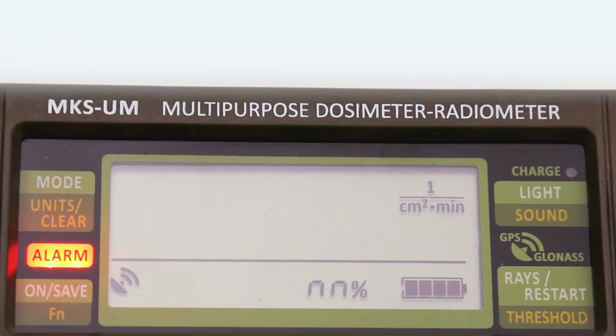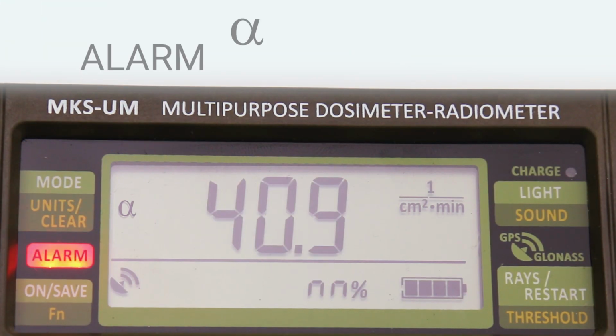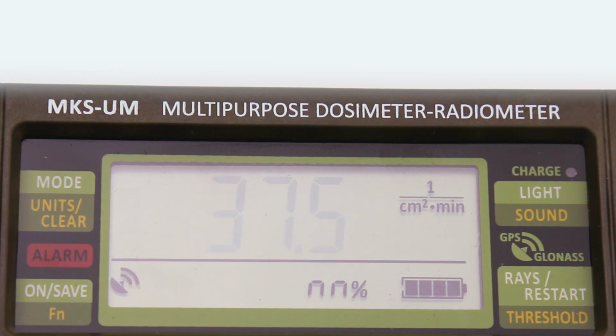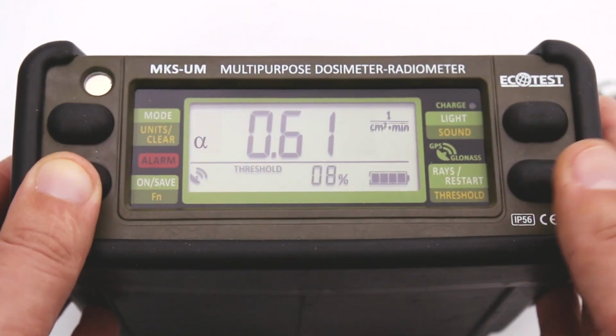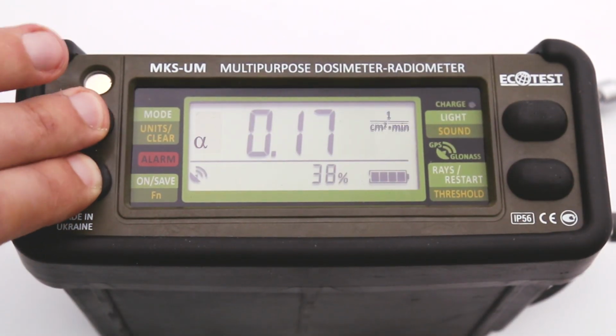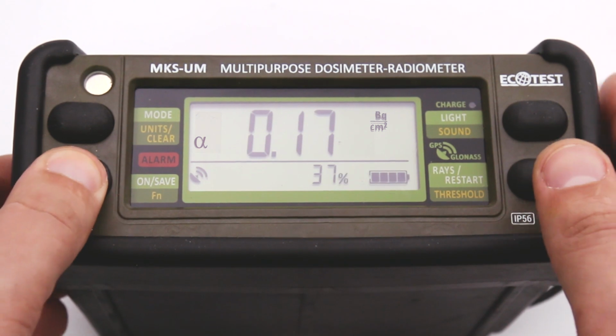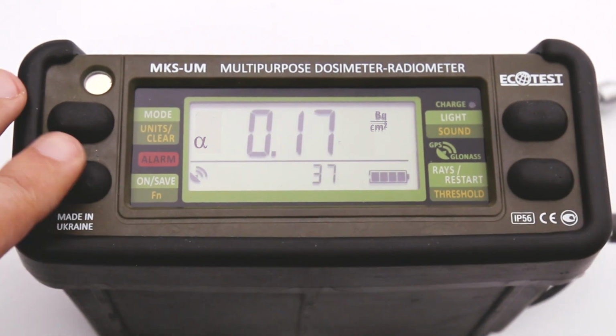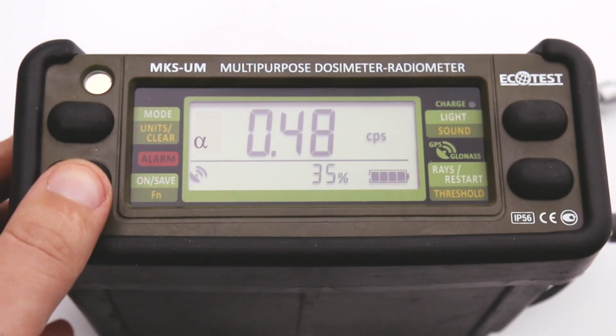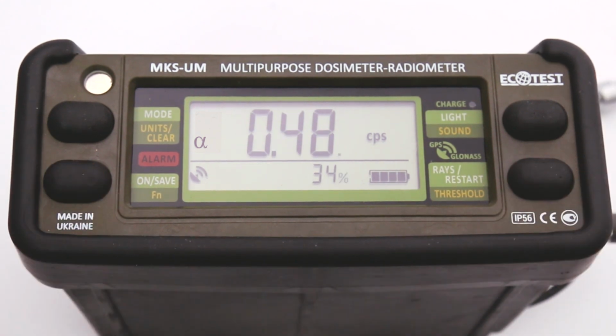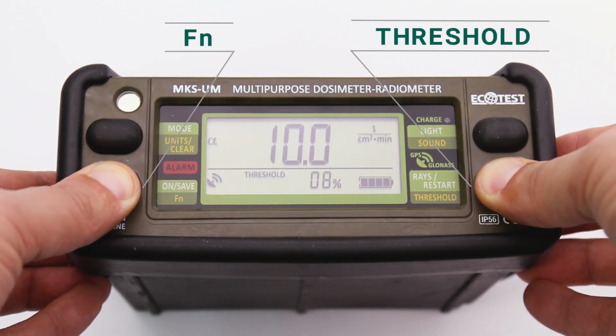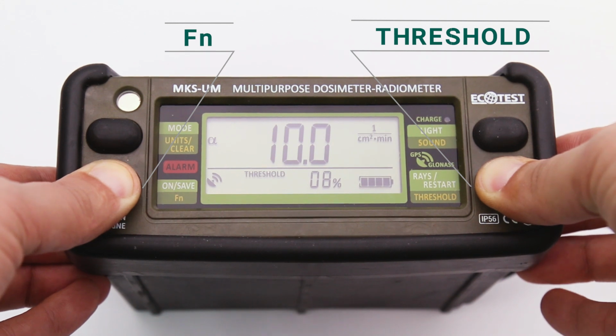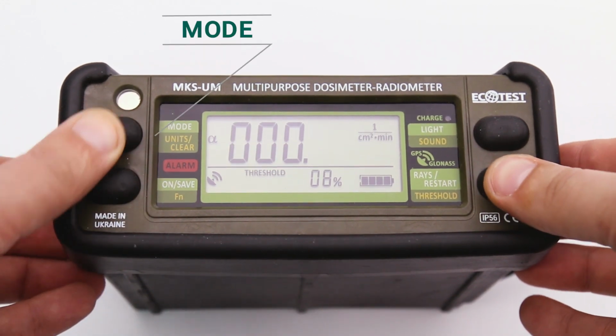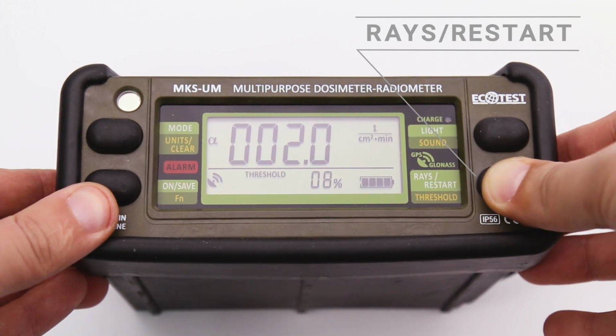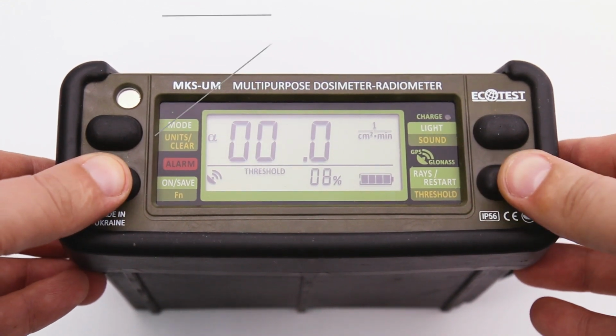When the threshold level of the alpha radiation is exceeded, the sound and light alarms are activated. When measuring the alpha radiation, the device operates with 3 independent threshold levels. You can set different threshold levels for different measurement units. You can view and set the threshold level and program statistical error for alpha radiation in the same way as for the dose rate of the photon ionizing radiation.